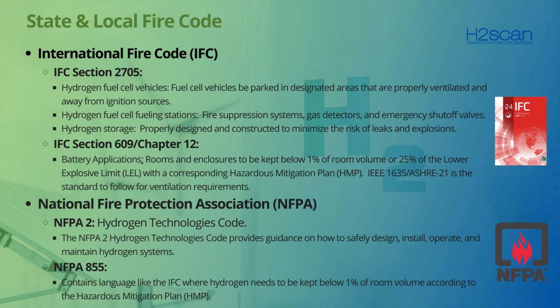There's also the corresponding IEEE 1635 ASHRAE 21 joint document between IEEE and ASHRAE that identifies the ventilation standards and requirements for battery rooms to meet the hazardous mitigation plan that's required for the fire code. And then, of course, the competing National Fire Protection Association model code also has the NFPA 2 for hydrogen technologies, and then NFPA 855 for stationary battery and energy storage systems.